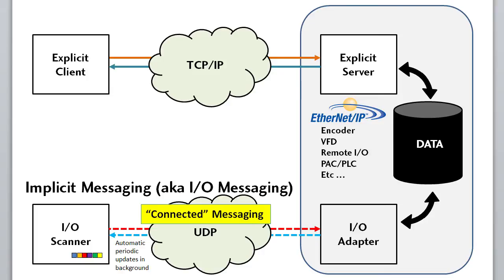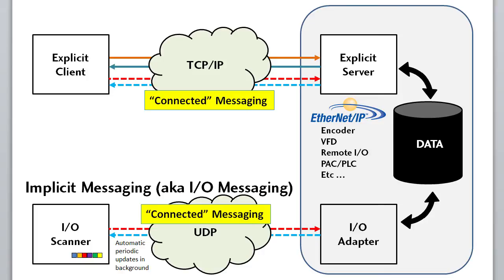Explicit messaging can also be set up as connected messaging to give you periodic updates, which is useful because it is still using the TCP/IP protocol to guarantee message delivery. However, it adds a larger burden on the processor because it has a lot more bulk in the messages and handshaking, which you usually don't need for periodic updates.